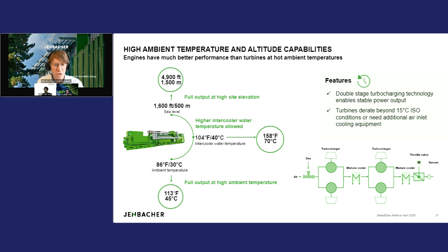This technology, with this special turbocharger system, allows us to run at the highest ambient temperatures possible in the market, and it also provides an advantage when installed at high elevation, where air demand is higher, with turbocharging technology helping to avoid derating. So depending on site conditions, our technology plays a very strong role and can outperform other technologies with regard to performance.